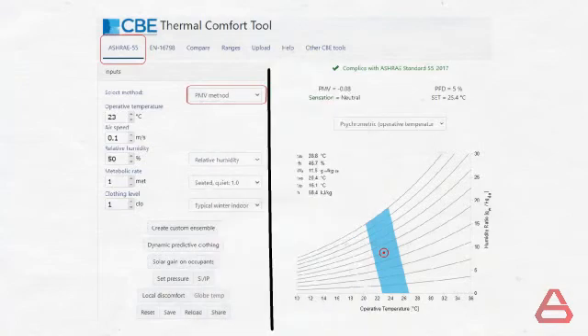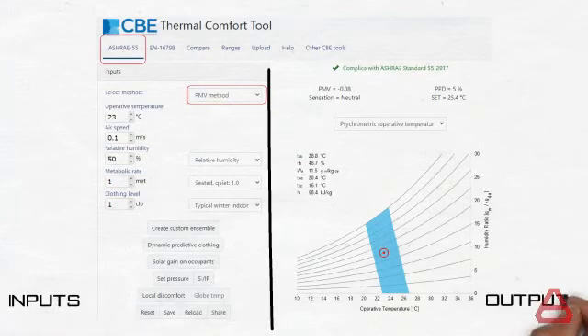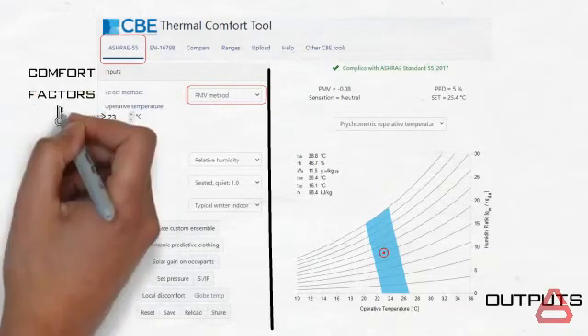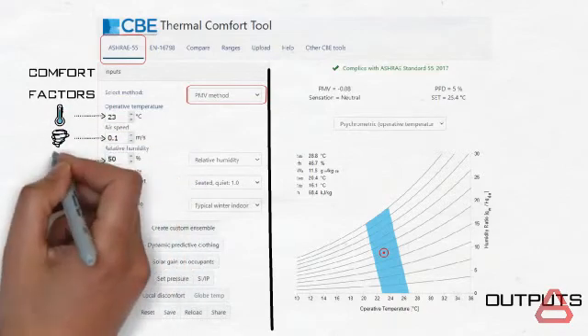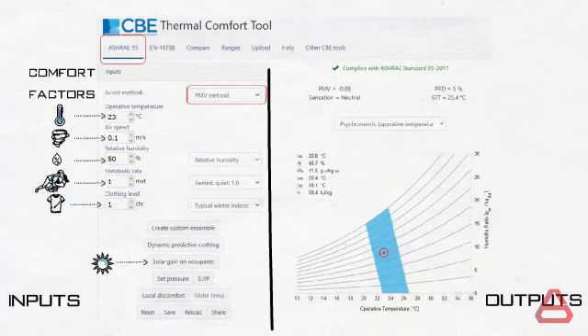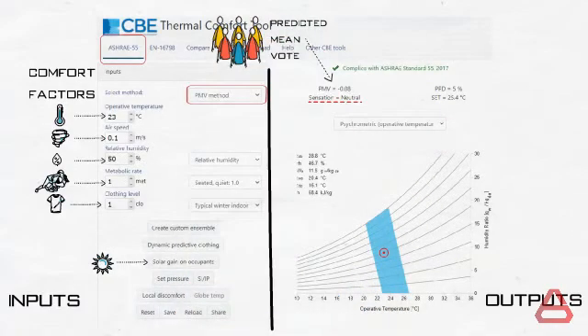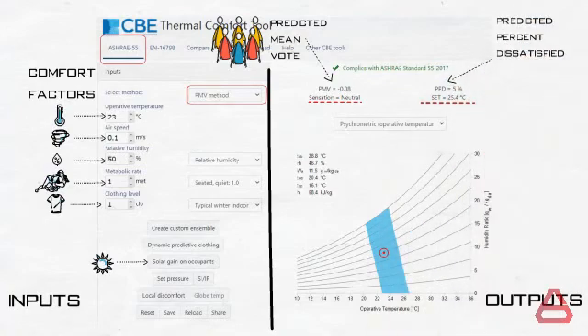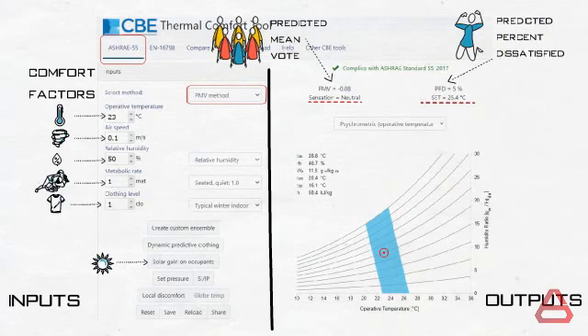The screen is divided into two main parts: inputs and outputs. In the inputs section, you have the factors that dictate human comfort — temperature, airspeed, relative humidity, metabolic rate which reflects activity, clothing level, and the mean radiant temperature, though we will ignore the last one in our case. On the right side you have the output or results section. Here you can see the PMV number generated based on the set inputs, and also the PPD, or Predicted Percentage Dissatisfied, which estimates the percent of people that would report dissatisfaction under similar conditions.